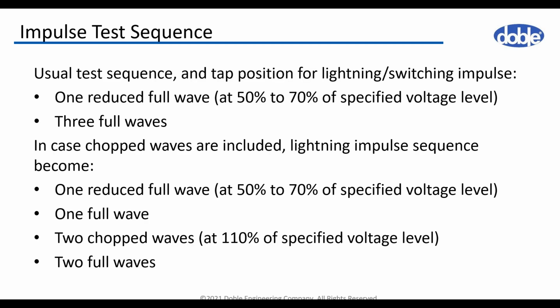The usual test sequence for full lightning impulse consists of one reduced or reference impulse and 3 full test voltage impulses. In case chopped wave is required, then the sequence differs a little bit, but it consists of one reduced shot followed by one full, 2 chopped waves, and the sequence completes with 2 full waves.